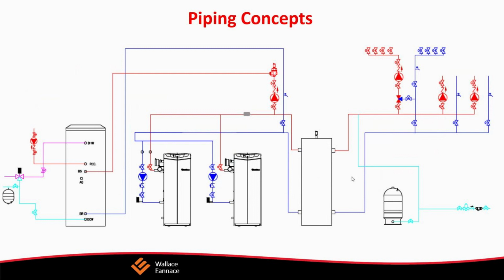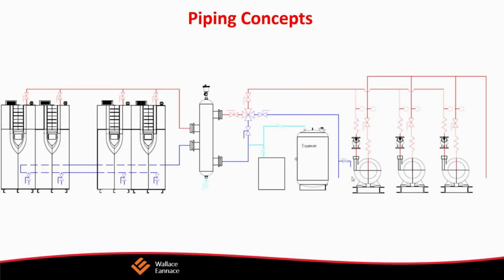Again, same thing, except here we have multiple zones. Same thing. We're always pumping away from the primary secondary headers, which is hooked up to the expansion tank. Here we see larger pumps with the large scale end suction pumps, and again, same situation. Once again, you can see, now this is interesting. Instead of using a primary secondary header, we used a buffer tank.